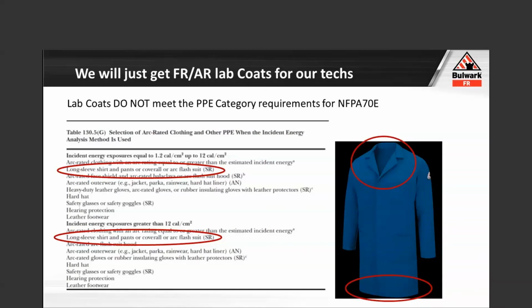The only place a lab coat should be utilized is in the exact description title of the garment - it is a lab coat. Though these fabrics may have the same arc ratings as shirts, pants, and coveralls, the design of the actual garment does not allow it to be used where you need protection from an arc flash. The design has a huge opening in and around the neck area, where if I had fuel sitting underneath - aka my 100% cotton work clothing - where do you think that arc and all that heat and energy is going to go?